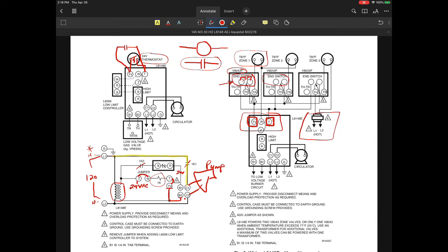You'll also notice that, and this is important to recognize, under no circumstances do you ever want to interfere or interconnect transformers. Be very careful with this. If you're going to have this transformer that is shown in this case, I would highly recommend getting a transformer big enough to power all of the zone valves and not use the internal transformer in the Aquastat. It's more from a diagnostic and a fail-safe type application.